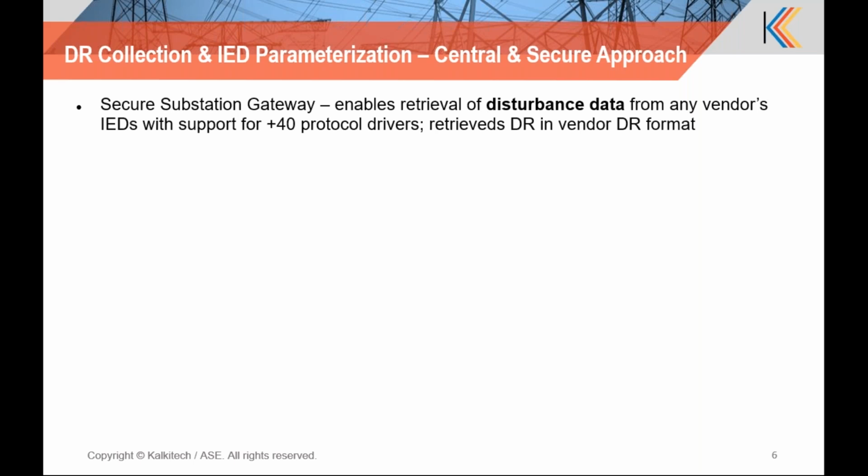For example, if a SEL relay is used, the SEL format is available, in which the COMTRADE format is preserved. If it is a Siemens relay and the protocol supported is 103, then 103 has a specific format. And if it is an ABB system, they have a format over the SPA protocol.